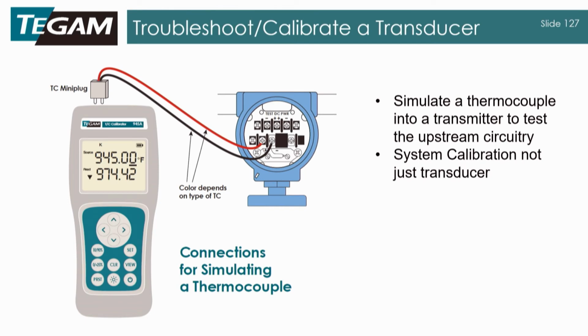If you're working in some industrial area, this is a very common application, and a lot of companies do this. So you have a simulation output, the source output. You basically set it up, say for type K, with a type K transducer. Then you can simulate a certain temperature range and see how the transducer responds. This is one way of covering wider ranges with your instrumentation without having to actually create a temperature source that's 1,000 degrees.